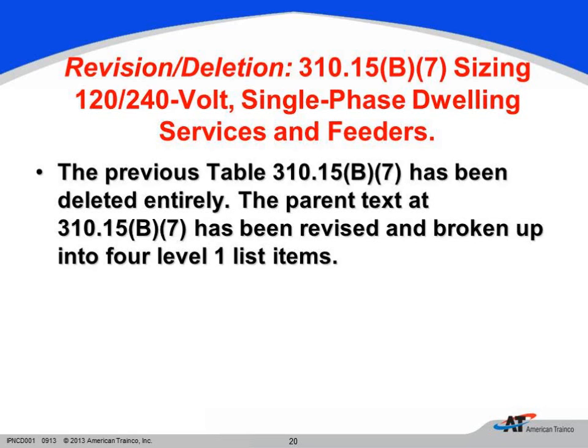So that's going to be quite a bit of change, and what we really should probably do is look in Annex D, and the example is going to be D7. It shows us how to do that calculation, and that's going to be very important, because forever all we've ever done is gone to that table, sized up the right entrance, and then we'd go and install that. So that's a little bit of a major change.